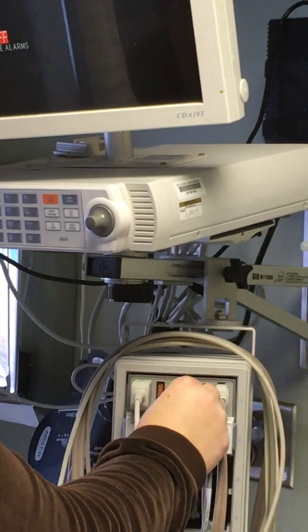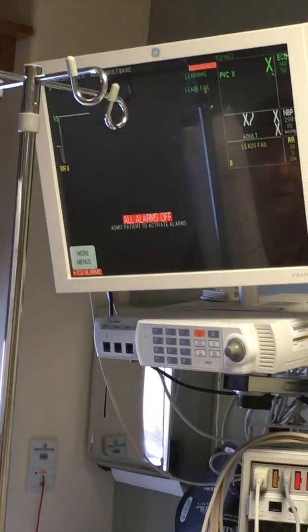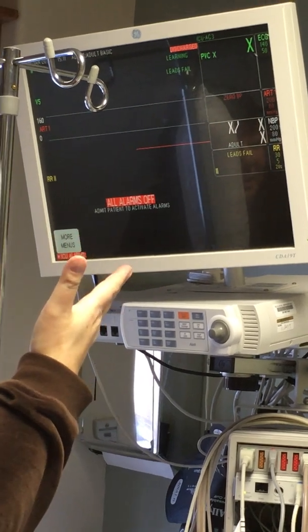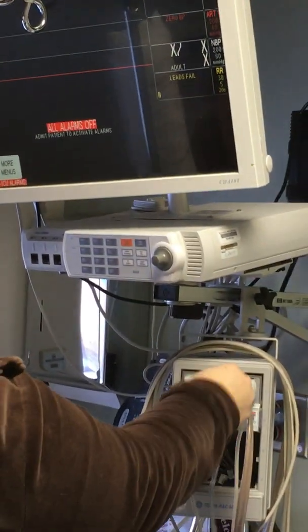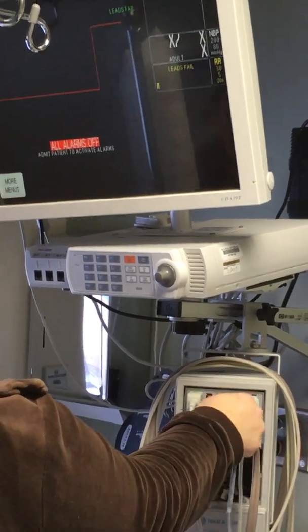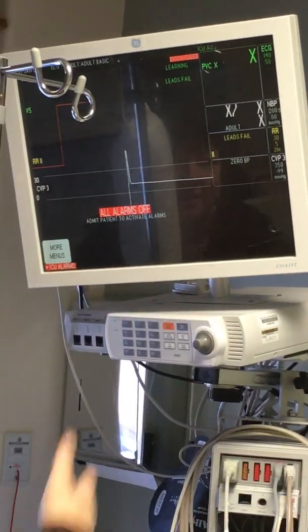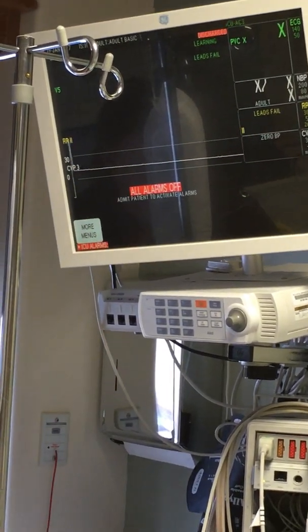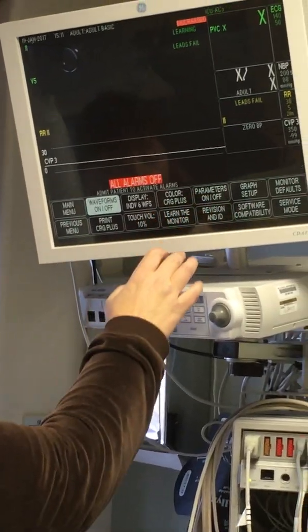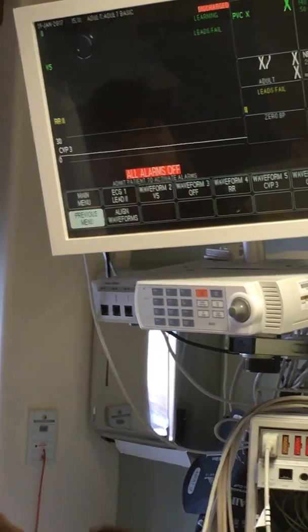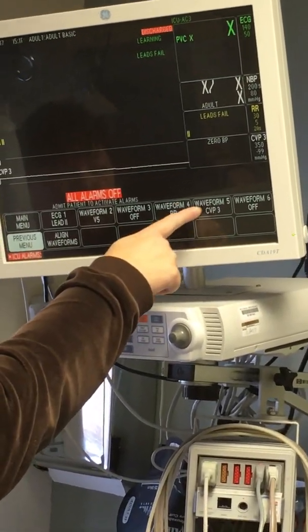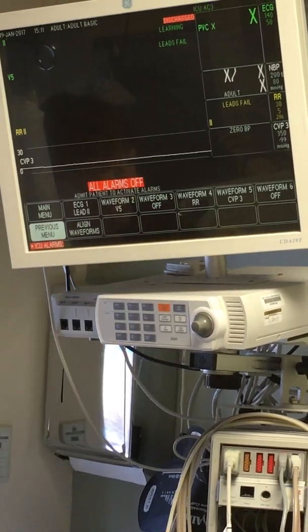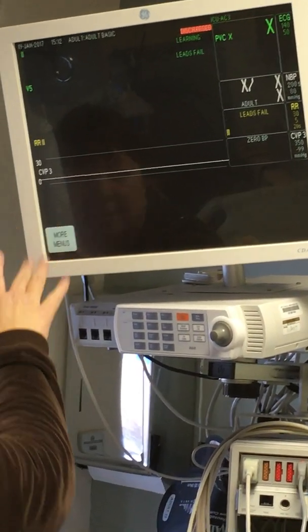So I'll come over to the monitor, and you want to plug your cable in. So let's try it over here. Oh, wait a minute, art line. If you're doing an art line, great, but if you're doing a CVP, wrong one. So let's try another one. There we go, perfect. CVP, and you've got a waveform. Let's say you didn't have a waveform. What you want to do is go to More Menus, Monitor Setup, and Waveforms on and off. CVP is right here, but if this said nothing and was blank and there was no CVP choice, you add it to one of your waveforms. That will make your waveform show up.